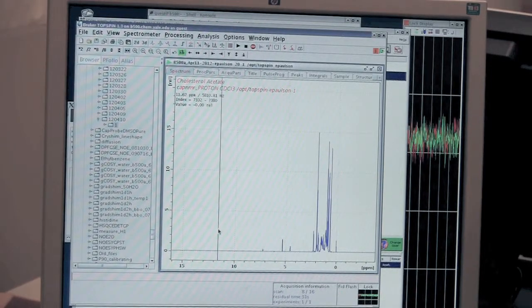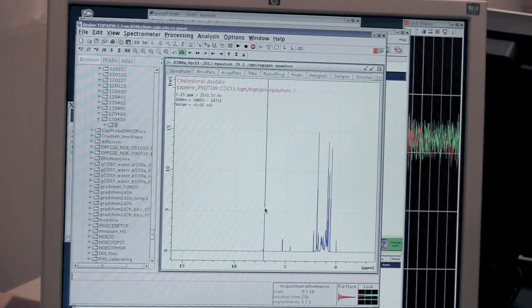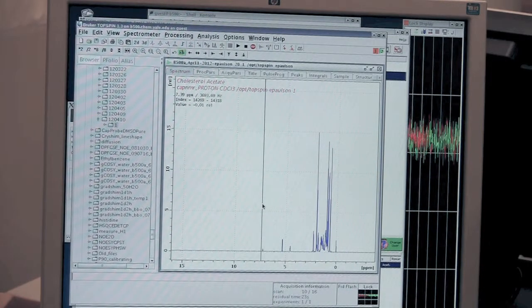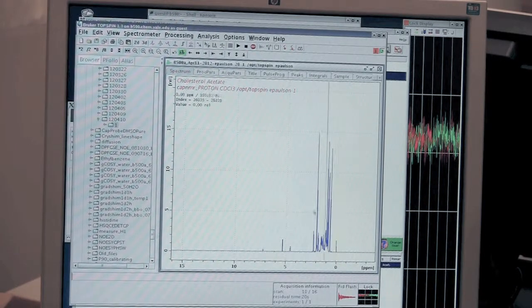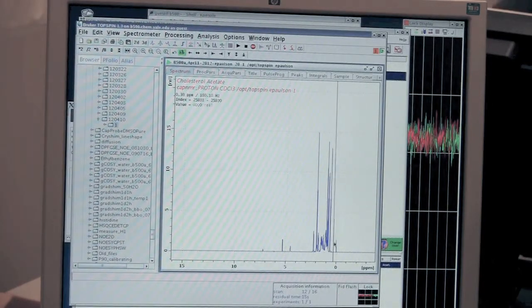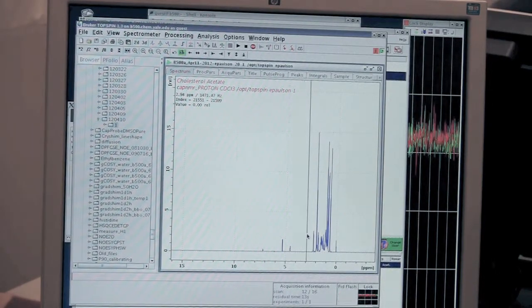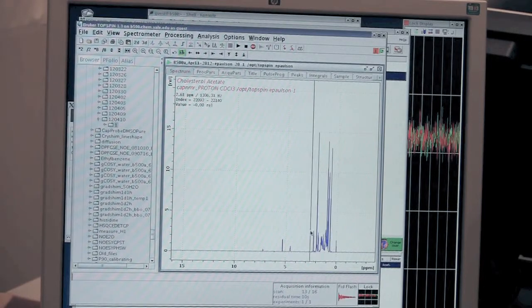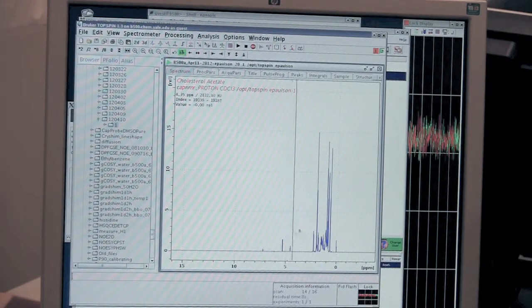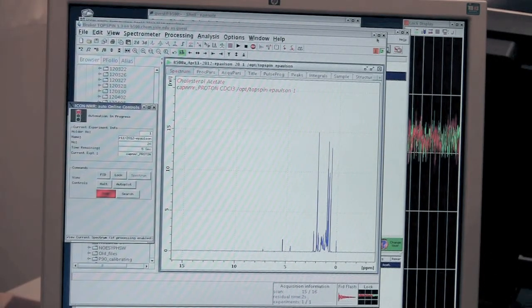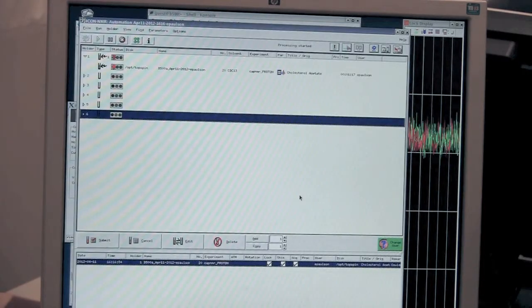And remember that the capillary NMR probe is less sensitive than a normal probe on a concentration basis, but the volume is much, much less than it is on a normal NMR probe, which gives you the advantage in signal for the total amount of sample. But remember that your concentration needs to be at least as high and probably twice as high as you would use on a normal NMR probe for the same amount of signal averaging. Once the spectrum is finished collecting, it's going to tell you to eject the sample, but again, you can just ignore that.